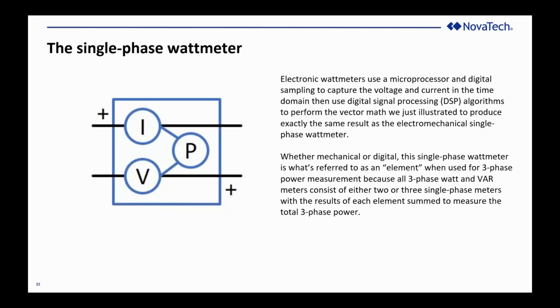So this is where we define the element. A single-phase wattmeter is an element. Whenever we talk about three-phase power, we're talking about either a two-element or a three-element meter. But I'd like to emphasize very strenuously that when I say the word element in that context, I'm always referring exactly to this functional block, this single-phase wattmeter. A single-phase VAR meter is the same thing with a 90-degree phase shift, so it's still the same function. Power factor is simply the ratio of the watts divided by the VA, so the mathematical relationship is all very straightforward. But the element is the element, and nothing changes. We don't do any magic between phases when we talk about a three-phase meter.